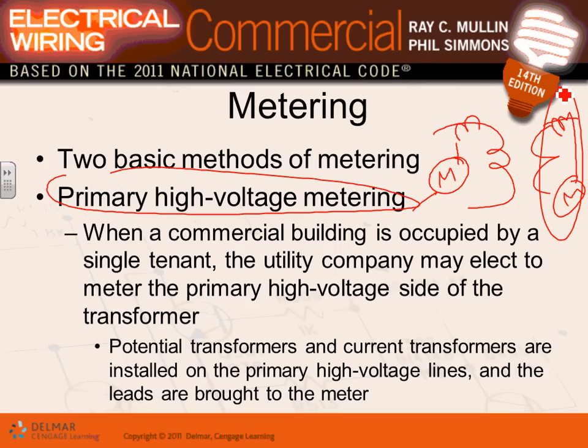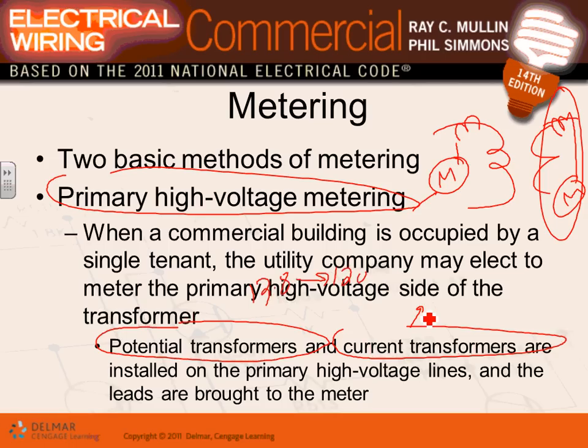The electric metering, in order to do the metering, guys, there's something called current transformers and potential transformers that you need. Potential transformers, guys, take the 13.8 and convert it to 120. Current transformers take 4,000 amp and convert it to 5 amps. And do you know why, Adam, they convert these? Now they put these into the meter. If you put 14,000 amp into a meter, what happened to your meter? Fried. If you put 13.8 into a meter, 13,800 volt in a meter, you fry it.